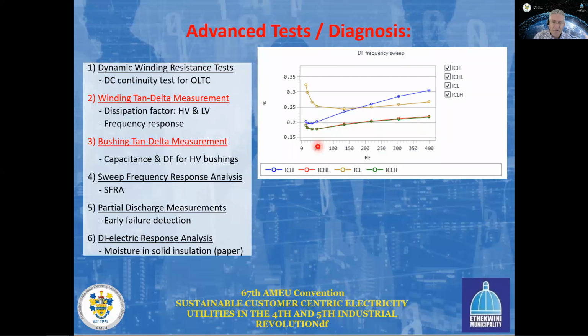So this measurement at 50 Hertz is firstly important, but secondly, the shape of this curve is also important, because a new transformer will show us an increasing shape, meaning that the tan delta values increase with frequency. And as the insulation deteriorates, this shape will change. And you can see here, for instance, for the ICL measurement, that this is already starting to show signs of degradation. And this will firstly obviously result in this measurement increasing, but also the shape of this curve is another order of confidence in terms of our tan delta measurement and our test results.